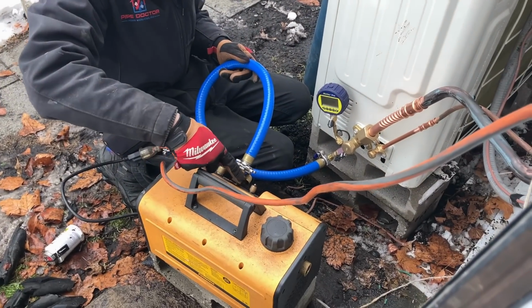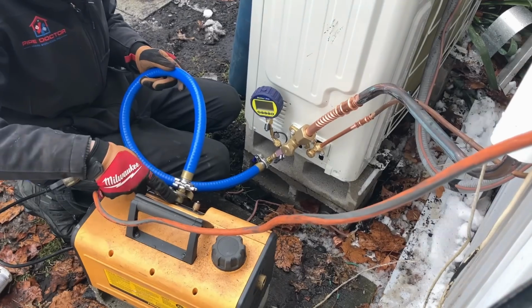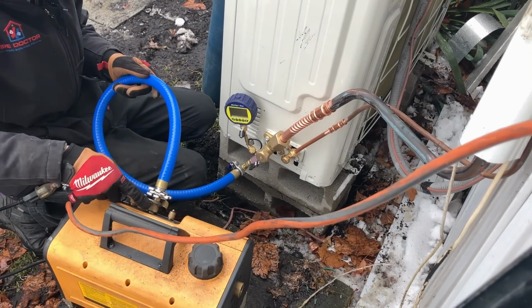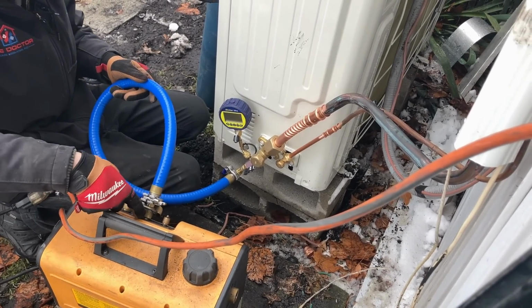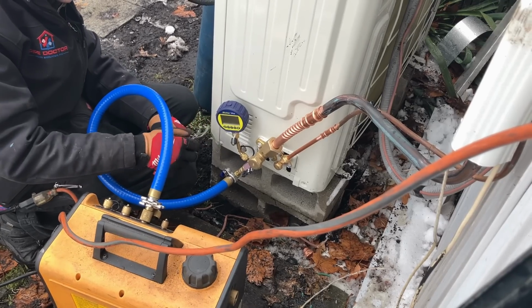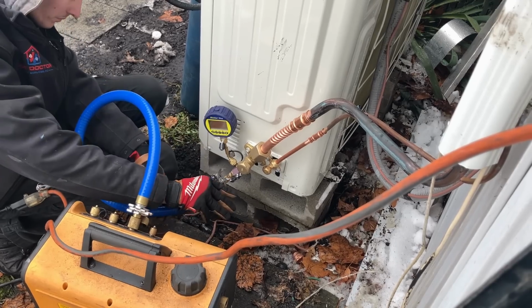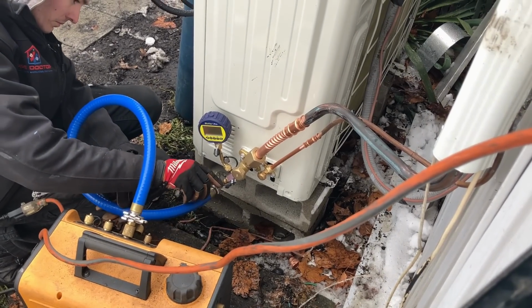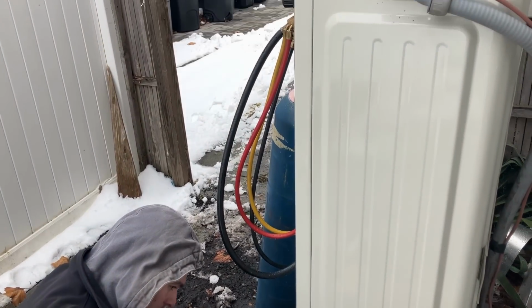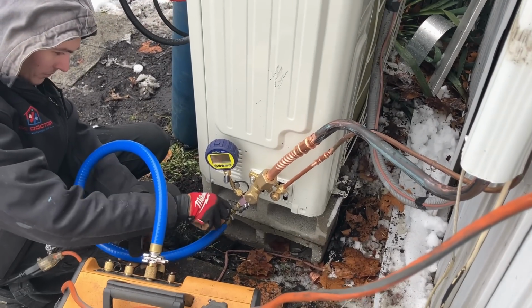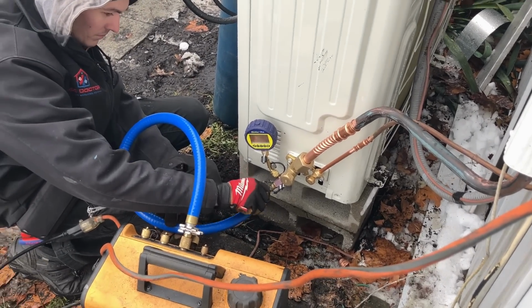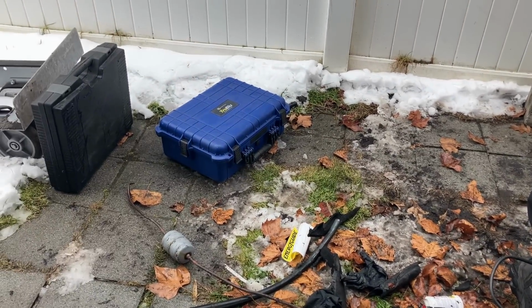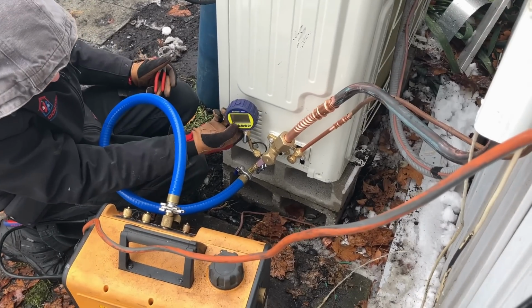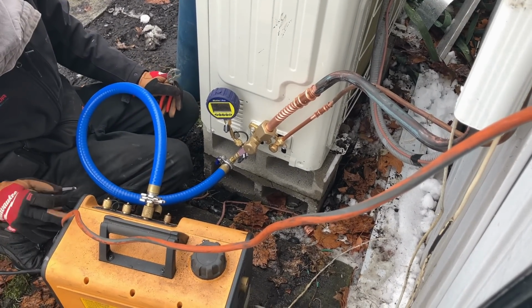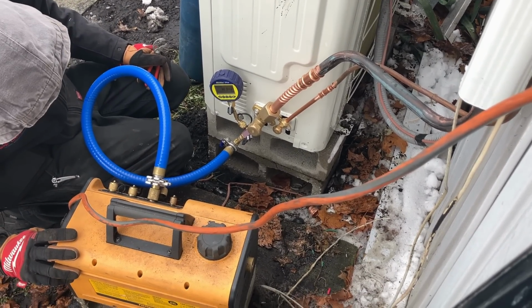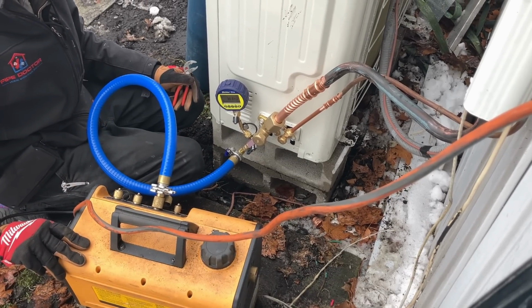All right, so we're now going to do the vacuum process. The outdoor condensing unit is connected to our 7/8 and 3/8 with the flare fittings, also utilizing the zoom lock. So there's no brazing, no need to flow nitrogen other than testing for leaks. We're using the AHU Tools True Blue evacuation kit. This allows us to pull a nice deep vacuum. Industry standard is 500, but my company would like to go to the teens.